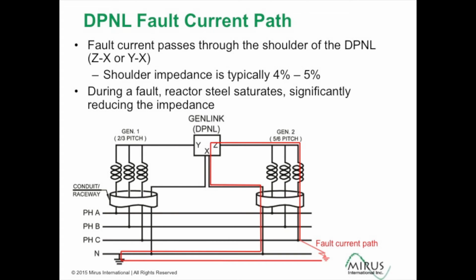So we look at the fault path. Red lines here showing a fault. If we had a phase to ground fault on one of the phases, fault current is going to go through the ground, back in through the system ground connection, back to the neutral, and across the shoulder of the DPNL, and then back to the generator. When it circulates like this, the protection in the system will detect the fault and trip and isolate the fault from the generator supply.